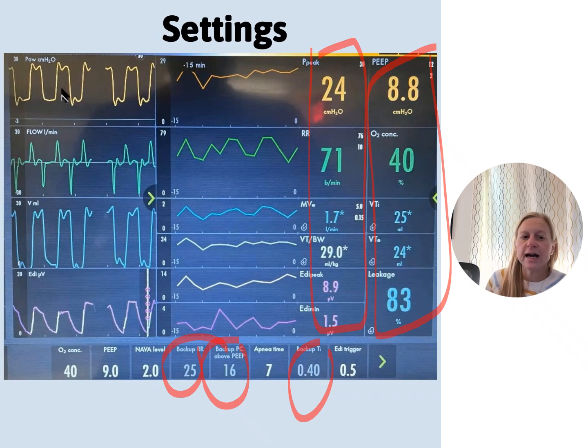So you see along the bottom, I've set the oxygen to 40%. I've got a PEEP of 9, a NAVA level of 2, an apnea time of 7, and an EDI trigger of 0.5. To me, this baby's actually doing pretty great. Maybe we're going to get off this situation soon or be able to wean to something else. We've got a backup rate of 25, pressure control of 16 above the PEEP. So that means your PIPs would probably come out to around 25, which is where we're at. And then we've got some measured values going on there. So that's what you're seeing on your screen. That's what the settings are. That's what I would be cued into as a NICU nurse.